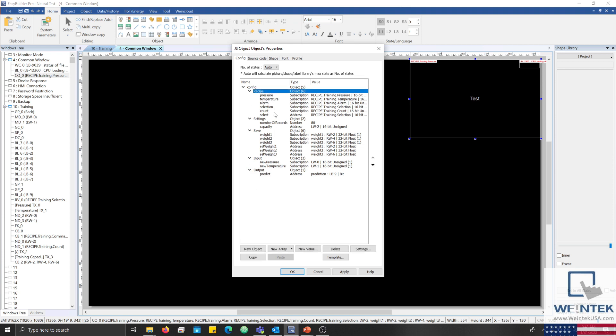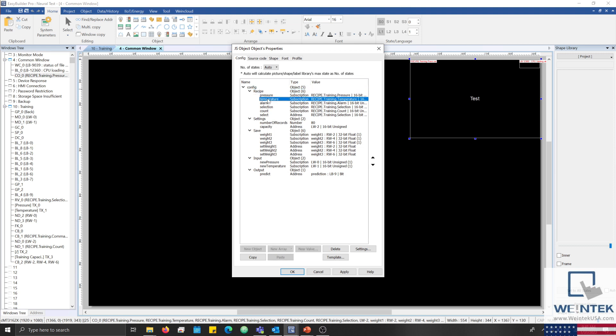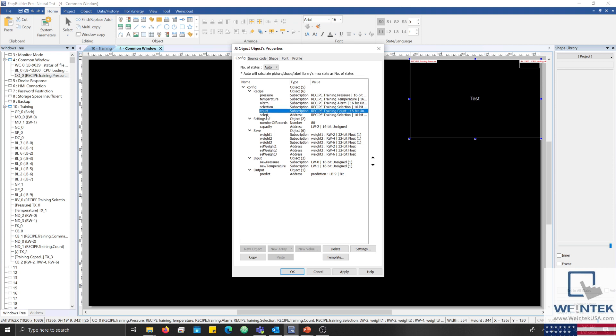Before we look at our source code, let's first discuss the purpose of each component within the config tab. Beginning with the recipe object, the subscriptions allow us to pull data from the recipe database and assign it to elements within a multi-dimensional array. The selection address is used to update the value within the recipe.selection register such that we select each row within the recipe database up to the training capacity.